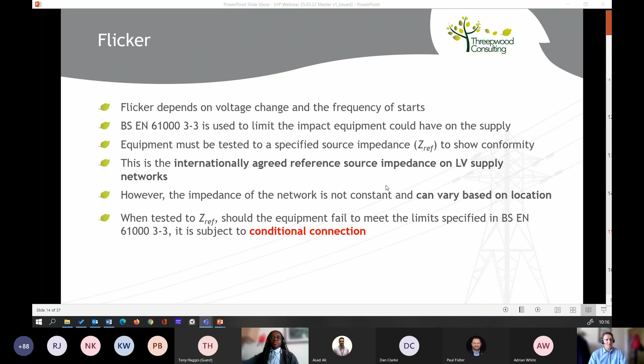What are the parameters then that are measured when you're evaluating flicker, Celica? The first two, short and long-term flicker, refer to flicker severity. The short-term flicker should not be greater than 1, whereas the long-term flicker should not be greater than 0.65. The other two parameters, referred to as the D parameters: first, your maximum steady state voltage change, which should not exceed 3.3%. Then the time accumulated where you have a maximum steady state voltage change greater than 3.3%, which should not be greater than 500 milliseconds. The last one, the absolute maximum voltage change or rapid voltage change, has different values. It can be 6, 4, or 7% based on the equipment, but we're going to keep it to 6% because this is a device that we can manually turn on and off.